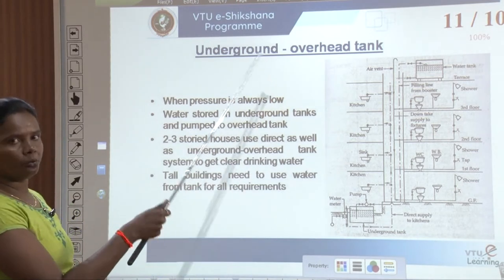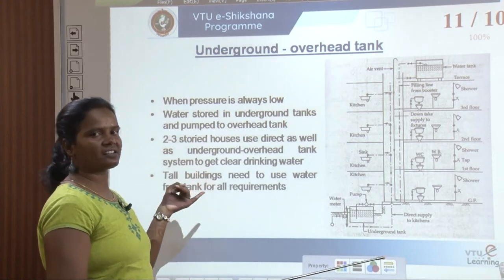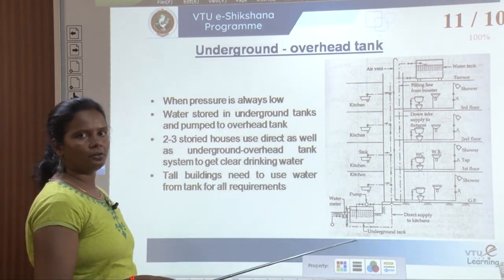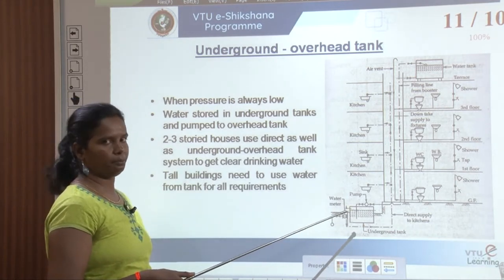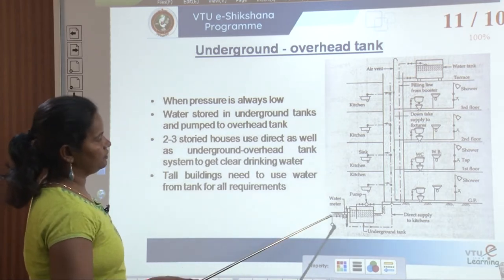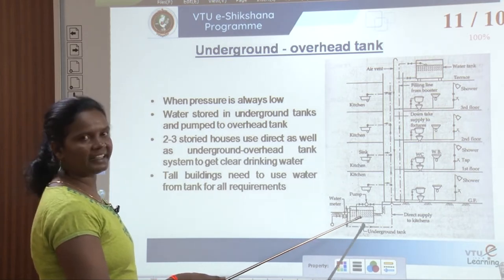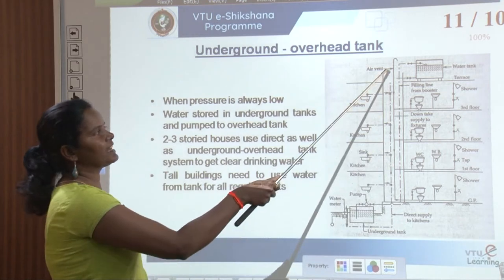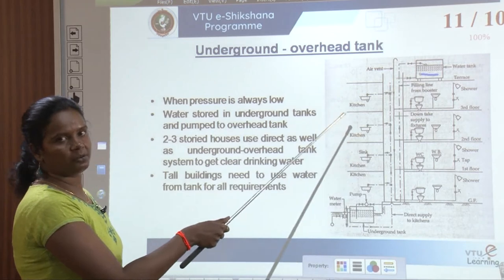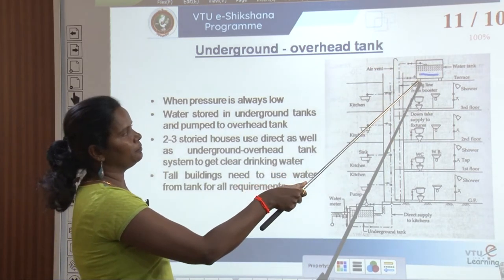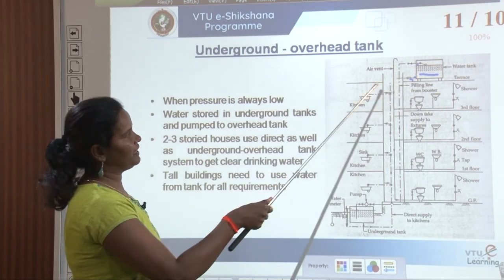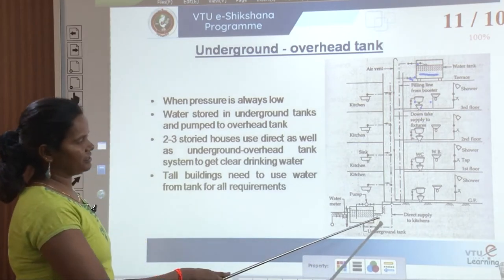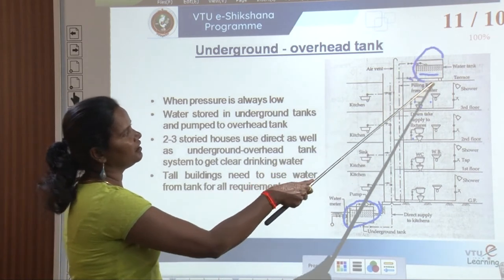The next is underground and overhead water tank — another form of indirect supply. From the city mains, after the water meter, water goes directly into the sump (underground water tank). From there, the water is transferred to the overhead water tank (OHT). Below the overhead tank, a pipe is connected to allow water to flow to all fixtures on each floor. This is the basic difference: we have both an underground and overhead water tank.